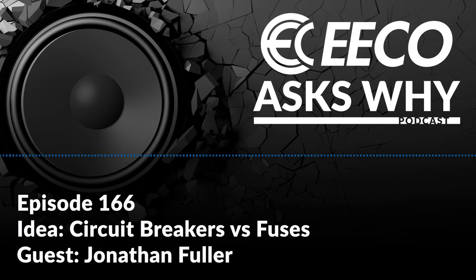Right. So your trip curve for your breaker is going to be a graph with two axes, your X and Y axes. Typically on one axis you're going to have time, and on the other axis, multiples of current. A lot of it depends on what application you're doing, what you're trying to protect. This graph shows you, for this time period and this multiple of current, I'm not going to trip. Once you exceed that curve, it's going to trip. You might have something that at half a second, you can go 200% of your rating and it won't trip. And then after that, it will trip instantaneously. Your curves are just going to be different for different applications and projects.